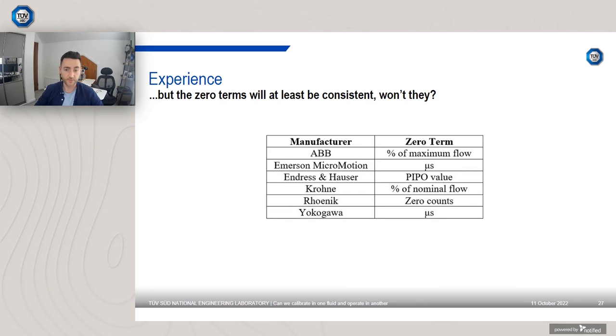Now, they have that zero stability that I showed you in the previous slide. I converted that into a usable term, kilograms per hour. However, they don't always present it in that manner. They often present it in a different term. So they have percentage of maximum flow, they have microseconds, they have PIPO value, which is just a term used by Hauser for the pipe in, pipe out value, and the difference between the two. Percentage of nominal flow, zero counts, and again microseconds.